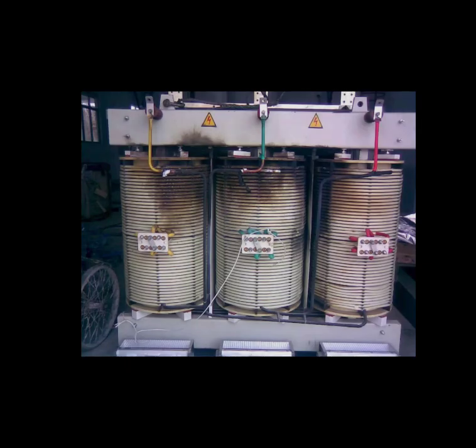As we have explored the dangerous aspect of current transformers, now let us analyze the implications of this open circuit of secondary circuit of current transformers. These implications include the following: Number one, risk of electric shock. The high voltage is hazardous and poses a serious risk of huge electric shock to personnel who may come into contact with the secondary circuit.